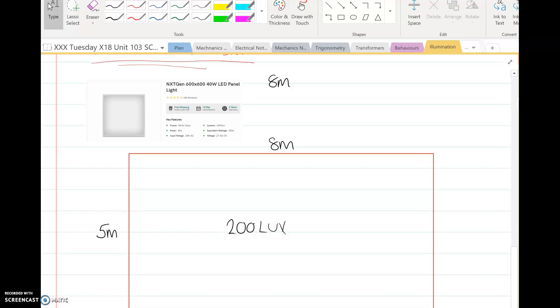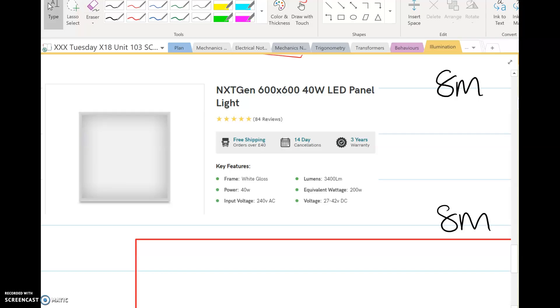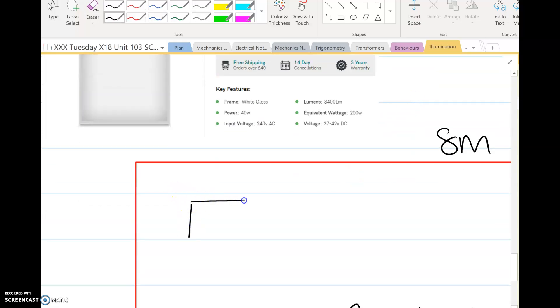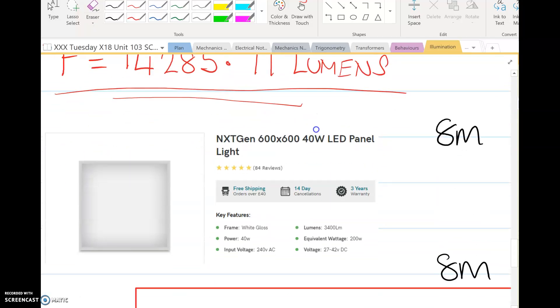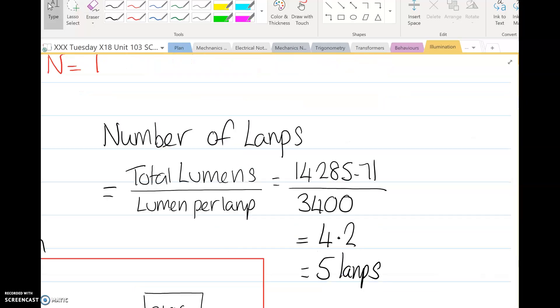So the question is, what sort of lamps are we going to fit? Well, I've just gone online. Let's say this was an office area, and you can see the power for each light is 40 watts. I've just searched for a 600 by 600 LED panel light. It's giving out lumens of 3,400, so one panel light is going to give out 3,400 lumens. How many lights do we need? Well, we divide 3,400 lumens into 14,285.7. So number of lamps is the total lumens required divided by the lumens per lamp. Our LED light, 3,400 lumens per lamp, divide the two, we get 4.2. Obviously you can't get 4.2 lamps, so that's five lamps.